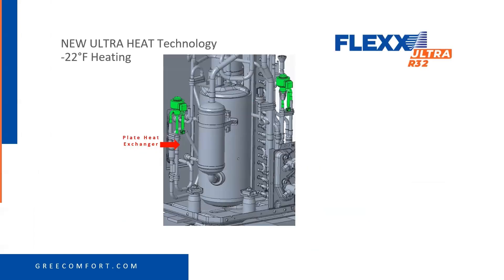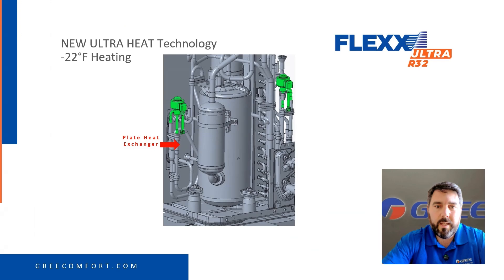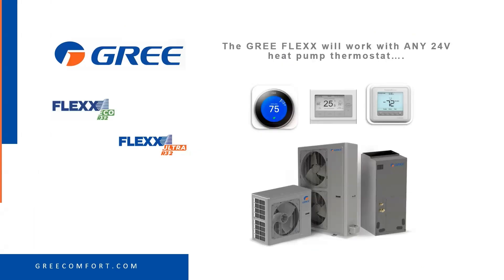Getting into the technology just a bit — it's a different type of technology than anyone's seen in the past with the UltraHeat. It uses a plate heat exchanger, and instead of just an open-closed solenoid to inject hot gas back into the compressor, it's using an EEV. The Gree Flexx, as we all know, will work with any 24-volt heat pump thermostat.